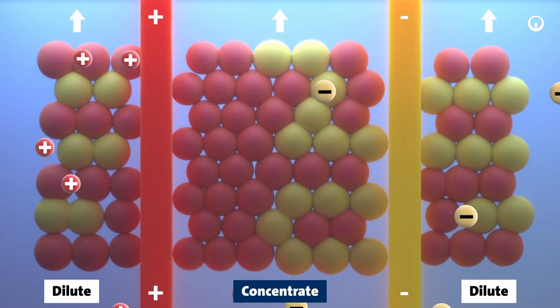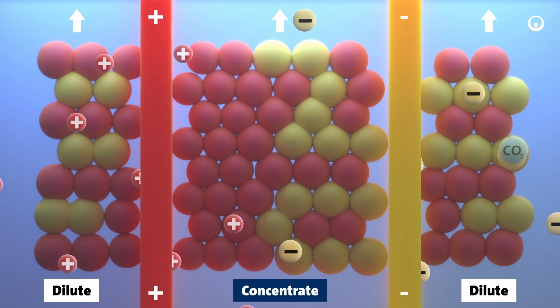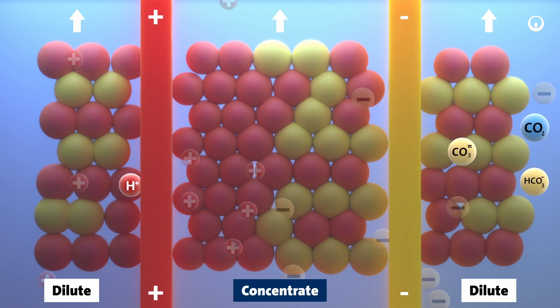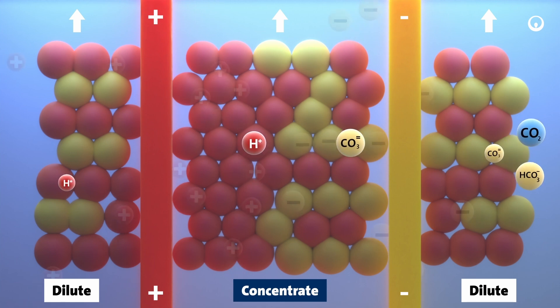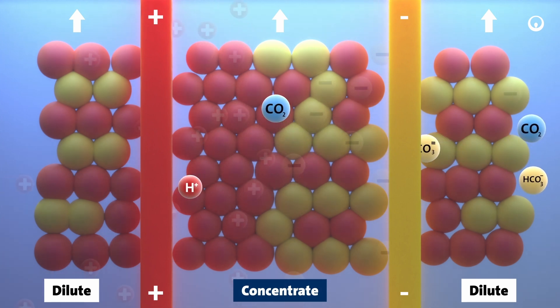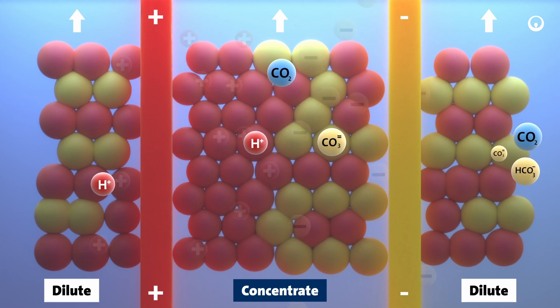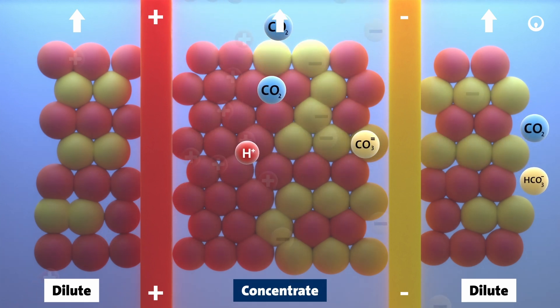The significant improvement to E-Cell EDI comes from innovation in the concentrate spacer design. By layering the cation resin near the membrane surface and mixing the cation and anion resin through the rest of the concentrate chamber, quality, efficiency, and hardness tolerance were dramatically improved — stopping CO2 back diffusion and conducting ion movement with less electrical consumption.